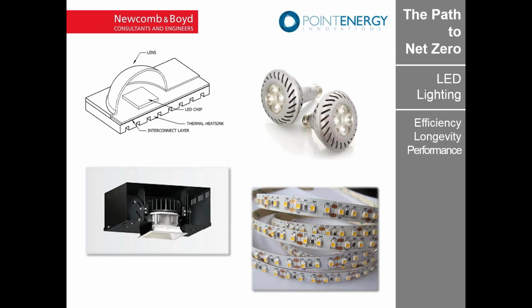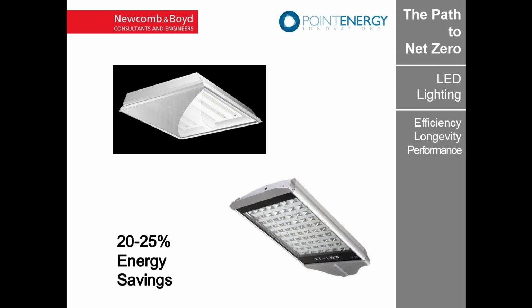LED technology is a conversation we probably couldn't even have 5 years ago. This has gone from lab work to figuring out how to maximize efficiency in these units. Five years ago we probably would have seen screw-in type fixtures or LED tape lights, and LED downlights have become prevalent. But nowadays, on the projects we're working on right now, we're seeing more general illumination type fixtures being implemented, including area lights for outdoor spaces. Averaging the numbers together, we're looking at a 20 to 25% energy savings over standard fluorescent, especially linear fluorescent lights, which are most common in the industry.